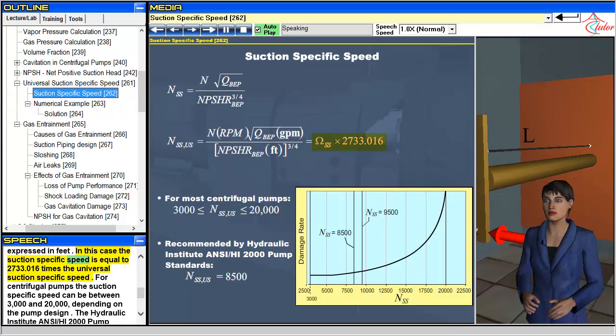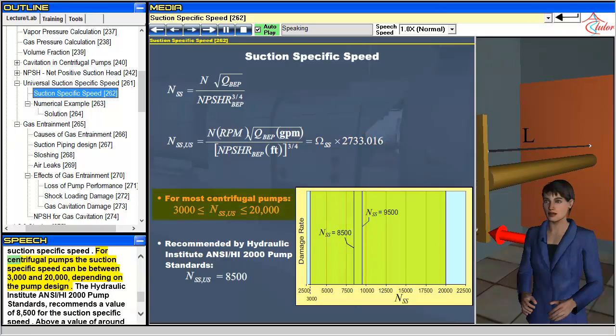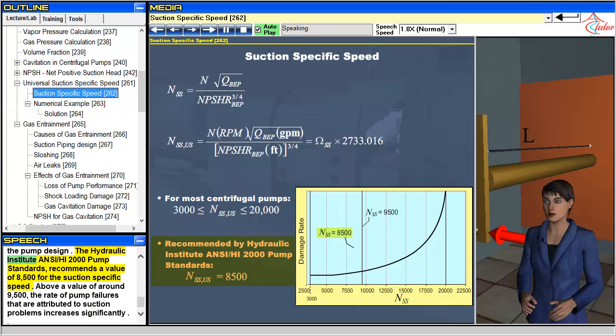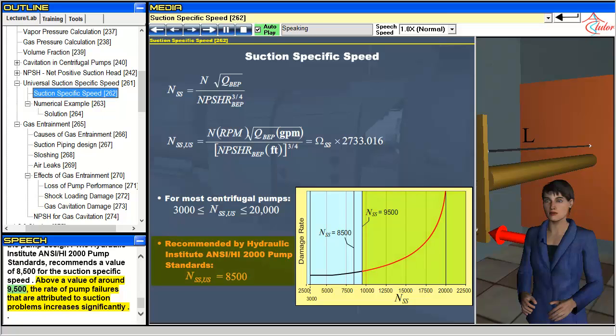In this case the suction-specific speed is equal to 2733.016 times the universal suction-specific speed. For centrifugal pumps the suction-specific speed can be between 3,000 and 20,000, depending on the pump design. The Hydraulic Institute ANSI/HI-2000 pump standards recommends a value of 8,500 for the suction-specific speed. Above a value of around 9,500, the rate of pump failures that are attributed to suction problems increases significantly.